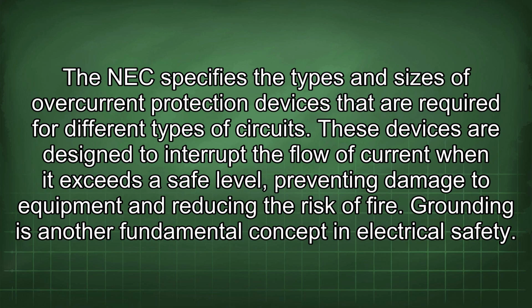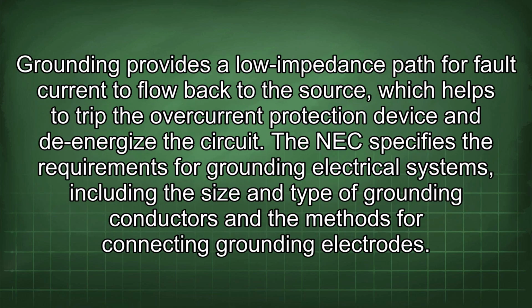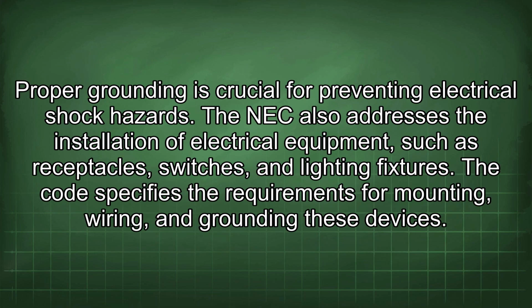Grounding is another fundamental concept in electrical safety. Grounding provides a low impedance path for fault current to flow back to the source, which helps trip the overcurrent protection device and de-energize the circuit. The NEC specifies the requirements for grounding electrical systems, including the size and type of grounding conductors and the methods for connecting grounding electrodes. Proper grounding is crucial for preventing electrical shock hazards.